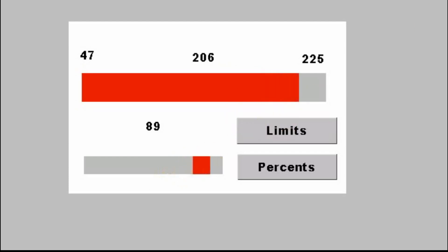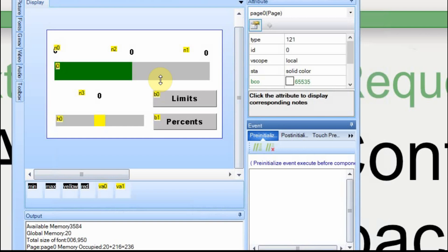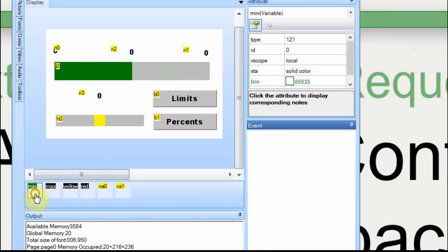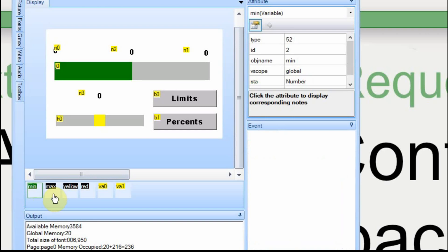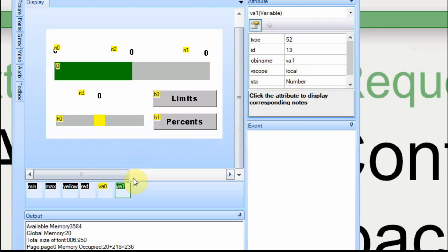On the front page I have six different variables. Instead of them being VA0, VA1, VA2, VA3, VA4, and VA5, I have changed the names to min, max, yellow, and red — because I'm making these global variables and I want to be able to identify them on the other pages just from memory. VA0 and VA1 are local variables, so I left those as VA0 and VA1. I use those for some logic down the road. You can change the object name to whatever you want and then refer to them, but be careful not to name it something that's already on your page.